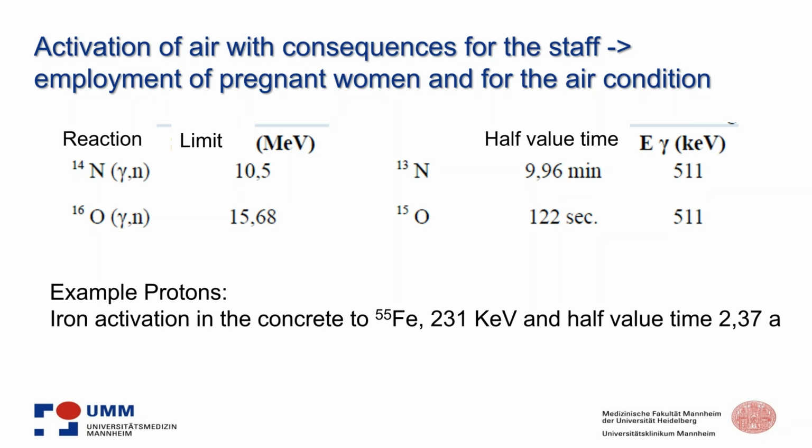Yeah, here is what I've talked about. You have an activation of air, and this has consequences for the staff, for example, the employment of pregnant women in these areas. If you have a linear accelerator with, let's say, 15 MeV, you have activation of air in the treatment room shortly after the treatment. You see the half-life of this nitrogen 14 product is around 10 minutes, and the oxygen one is only roughly 2 minutes.